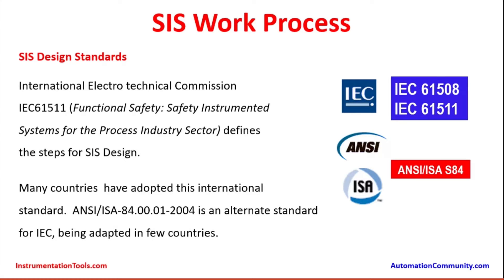For the SIS work process, we will understand the SIS design standards. The International Electrotechnical Commission, IEC, has standards 61511 and 61508 — these two are specifically for the safety instrumented system. IEC 61511 is for the process industry sector and defines the steps for SIS design. This is an international standard applied almost all over the globe, except in regions like the Americas and Canada, where they have the equivalent standard known as ANSI — American National Standards Institution — and ISA, the Instrument Society of America.